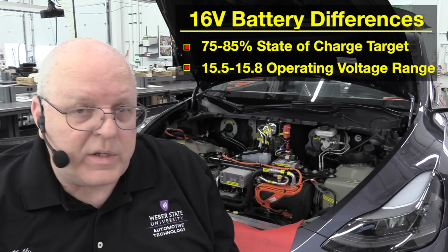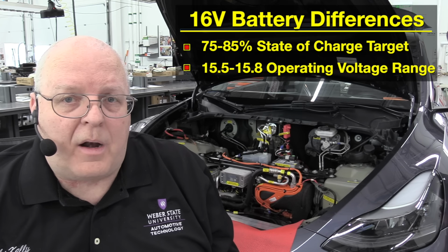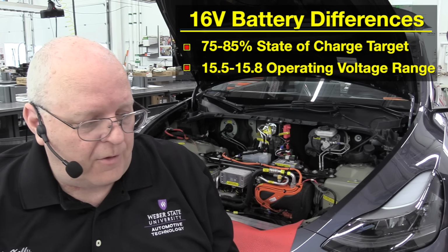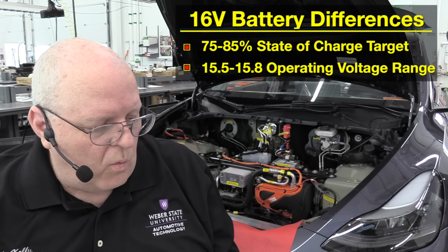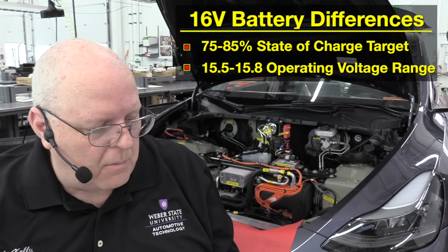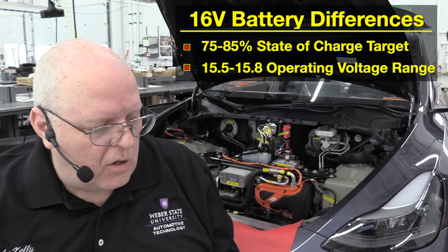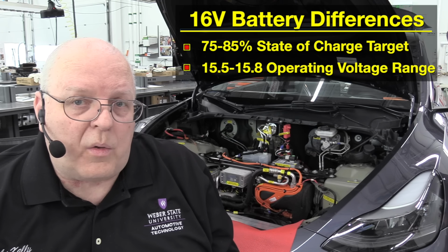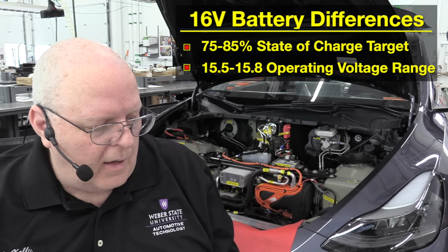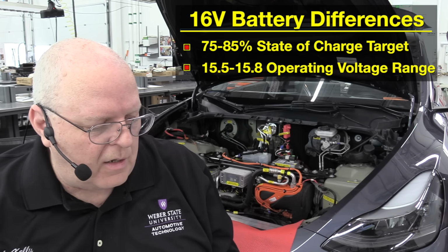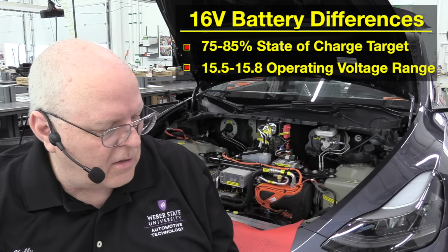The operating voltage range for the 16 volt battery is 15.5 to 15.8, whereas a lead acid battery while charging could be 13.2 all the way up to 15, and with a float charger it could be 13 to 13.9 depending on the temperature.